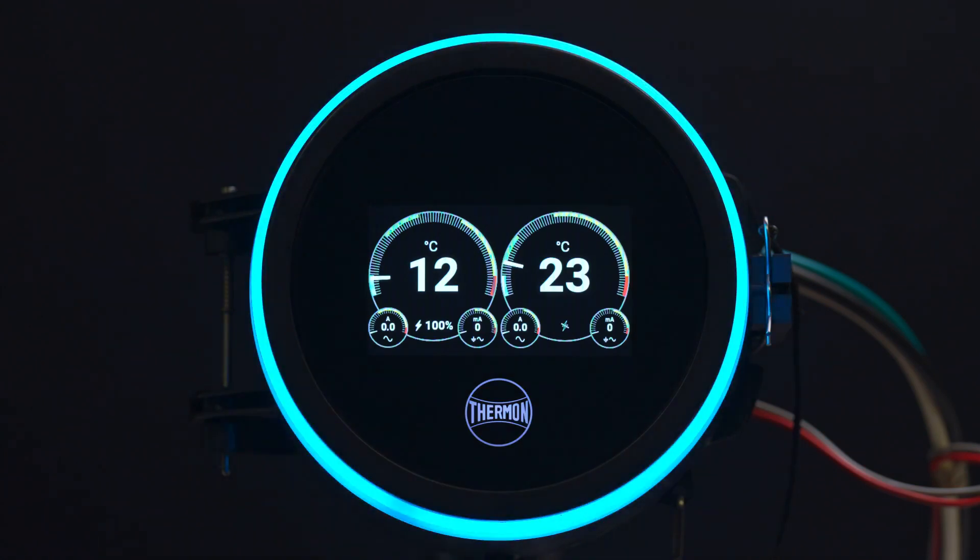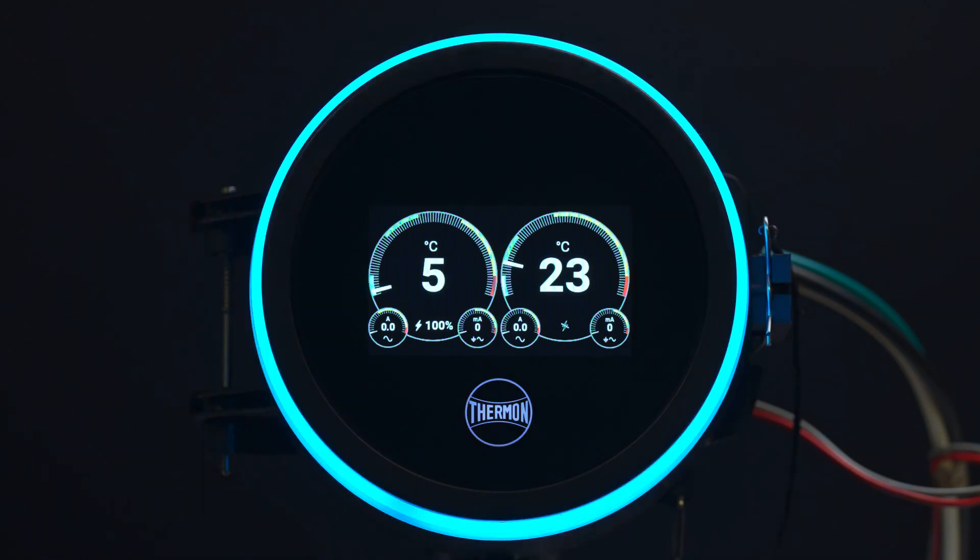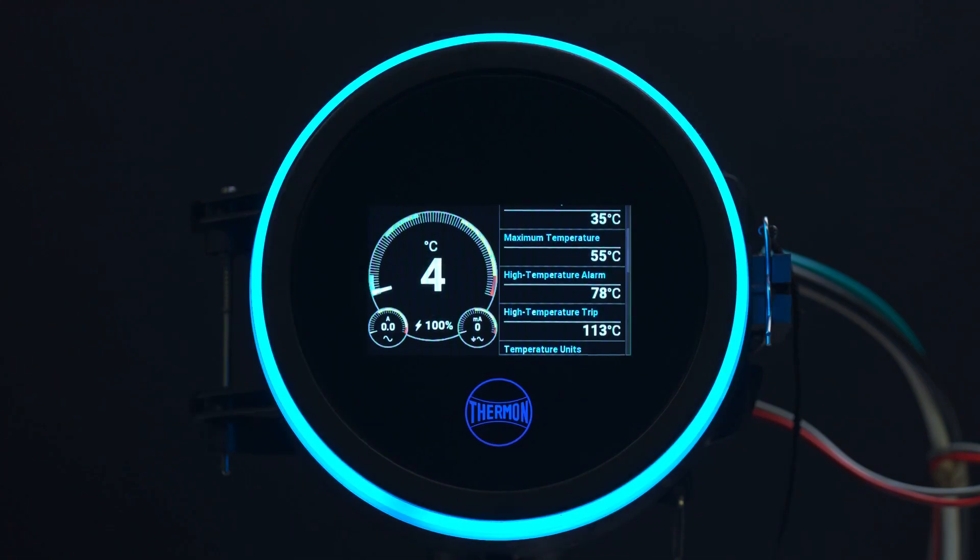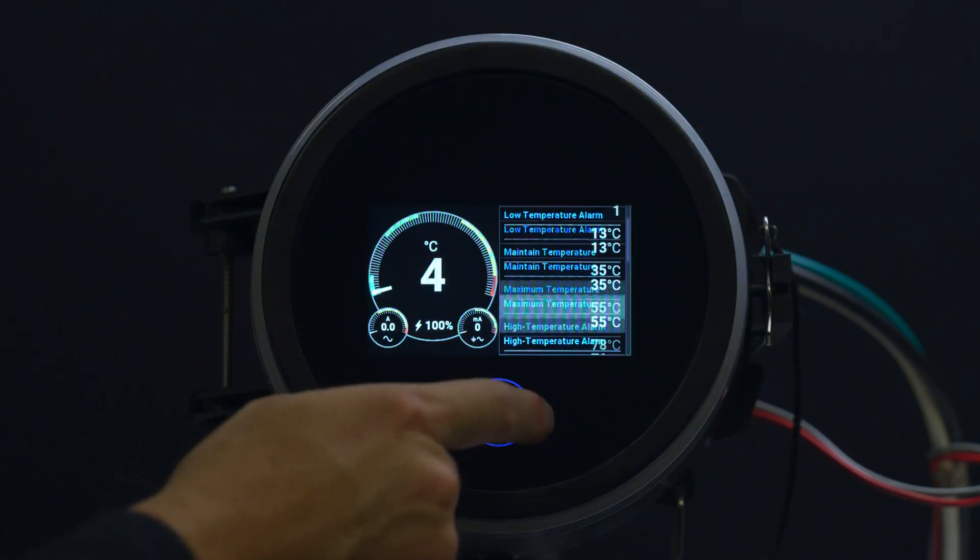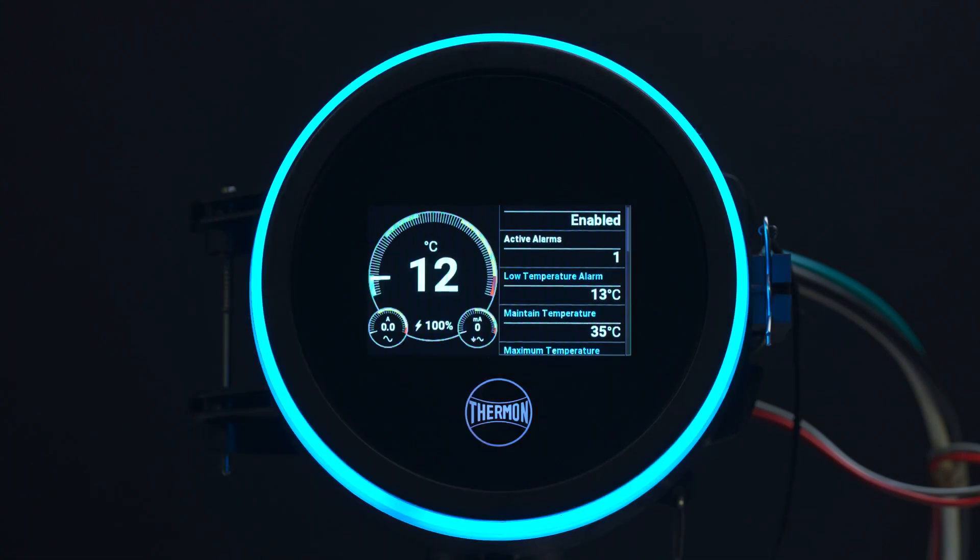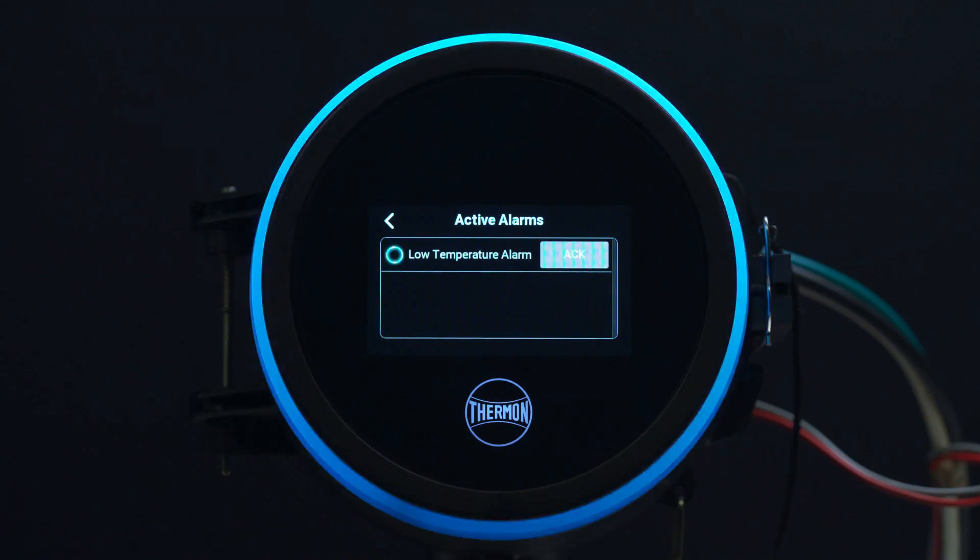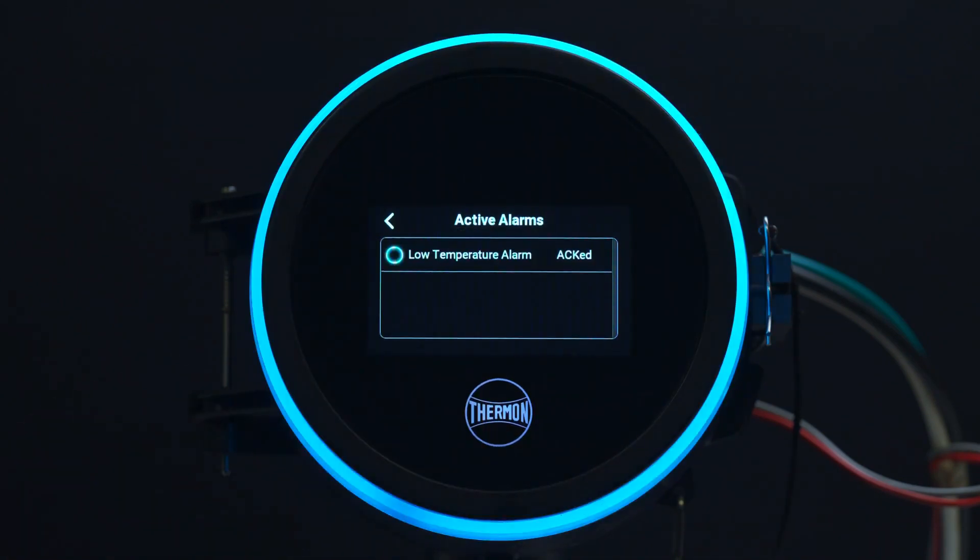Notice the light ring flashing blue and wiping to the left. The blue light wiping to the left indicates circuit number 1 is in a low temperature alarm state. Touch the gauge on the left for circuit number 1. At the top of the menu is active alarms. Touch active alarms and it will bring up a current list of active alarms. You can acknowledge all alarms or each alarm individually.